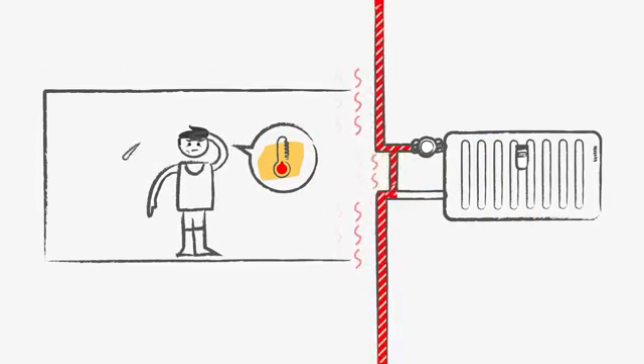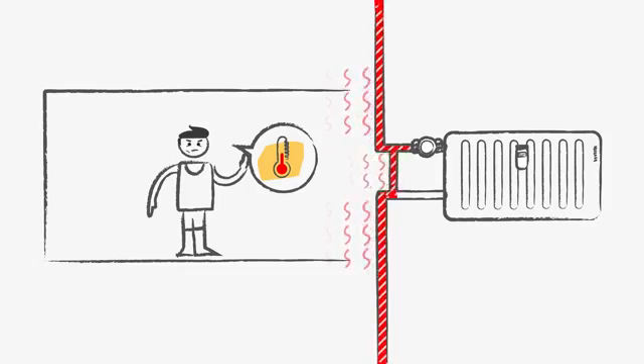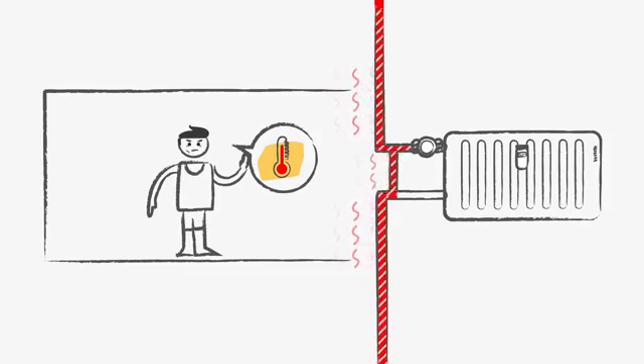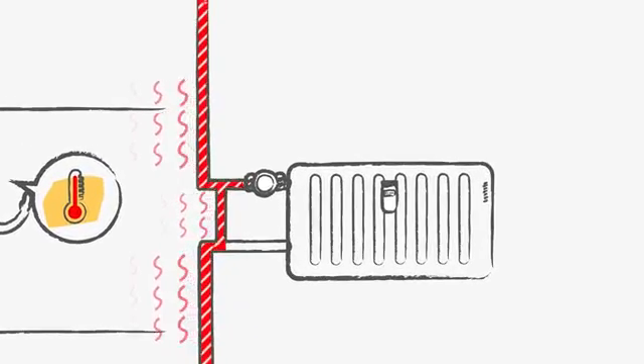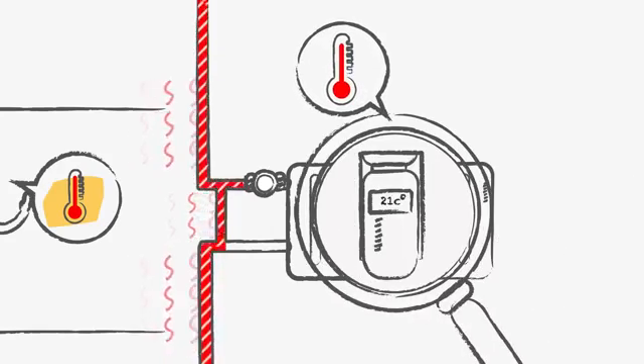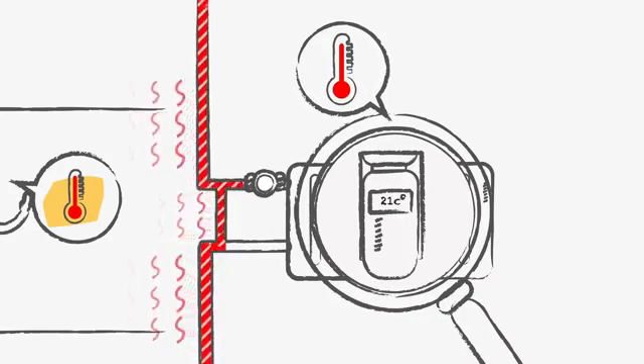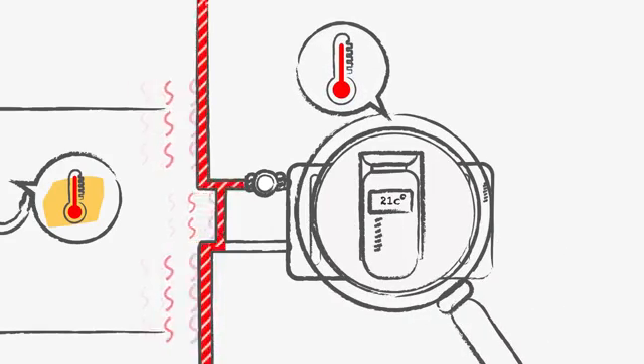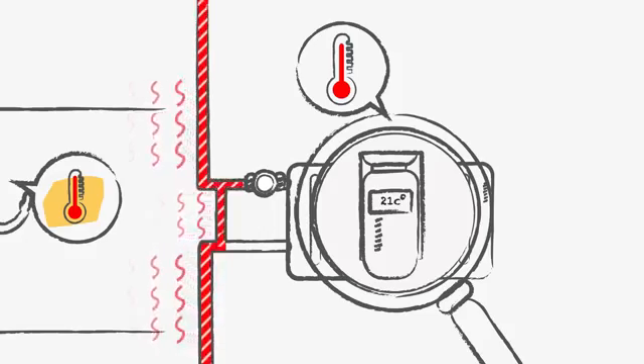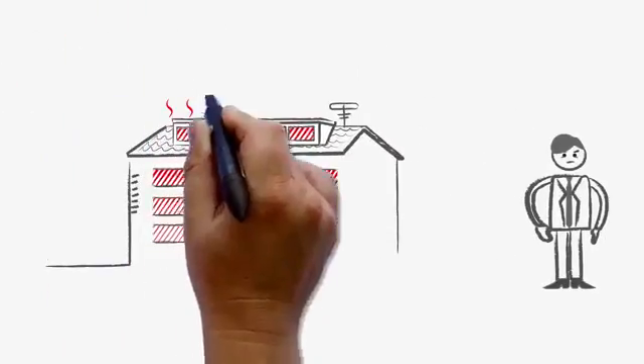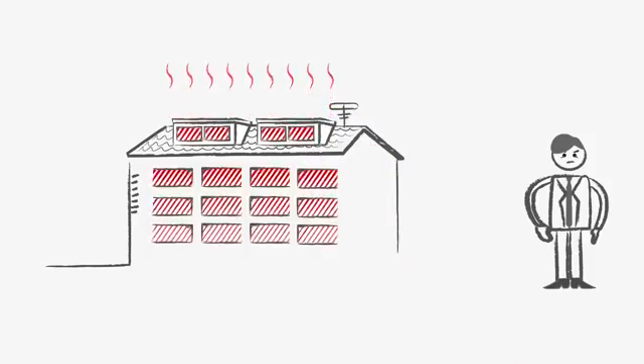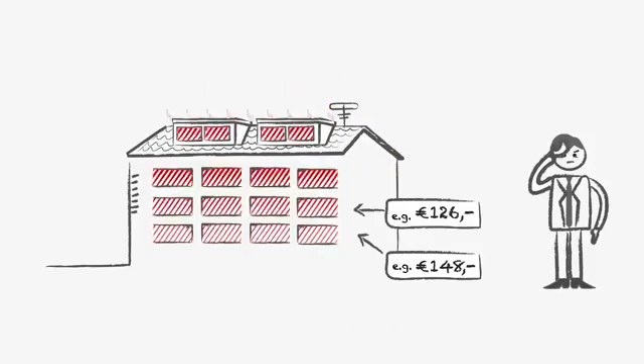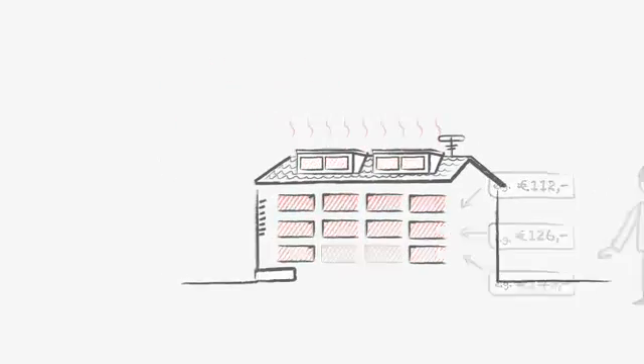Overheating can be explained by heat transmission from piping inside the rooms, causing the indoor temperature to rise. This consumption of heat is not detected by the heat allocators that are placed onto the radiator, leaving you with a building that is overheated, uses huge amounts of precious energy and causes headaches when it comes to fairly distributing costs amongst the residents.